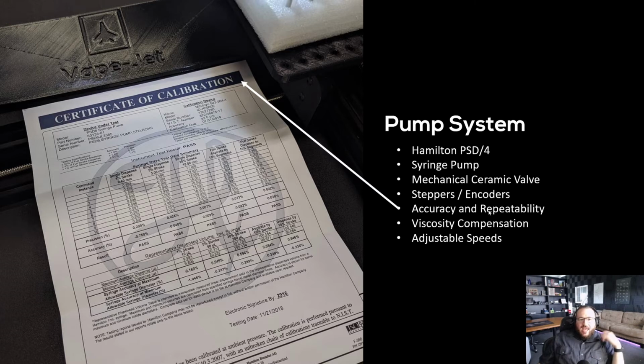So on the accuracy and repeatability of these pumps, each one is tested to NIST standards. You can backtrack the calibration that was done, which machine was used to calibrate it. These are all done by a third party prior to integration. But you can see the precision and accuracy of these pumps. We're typically doing a 30% stroke. Is down at 0.007 or 0.009%. Extremely accurate and repeatable pumps.